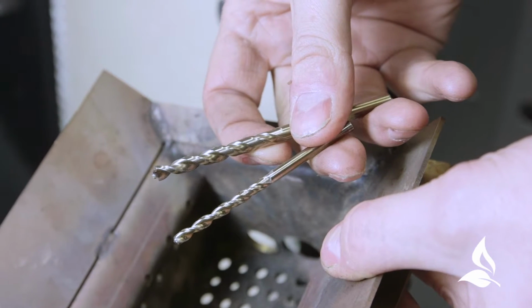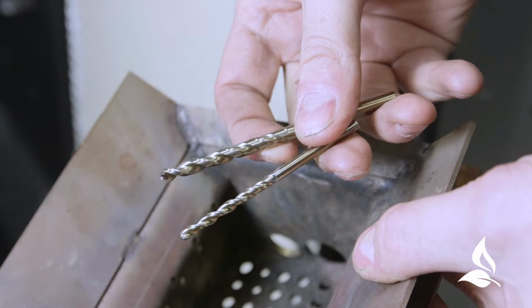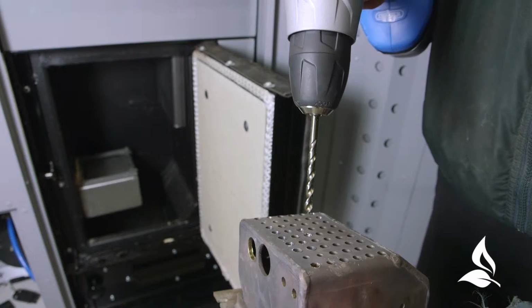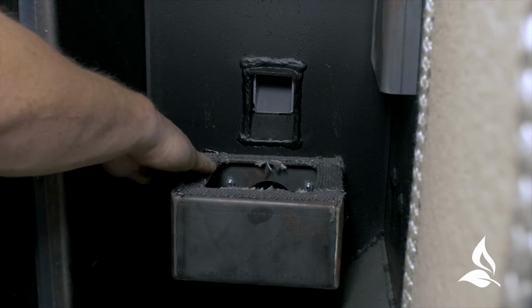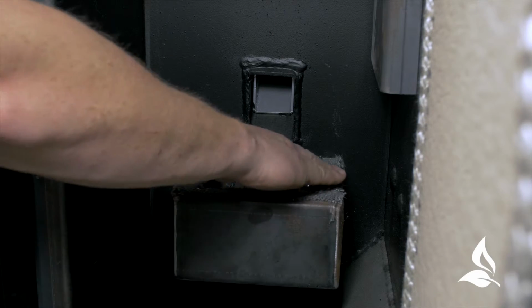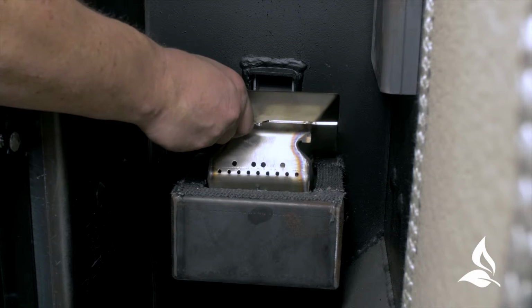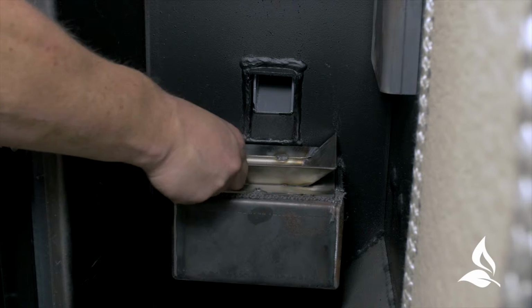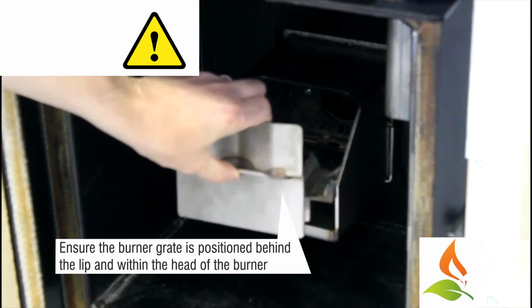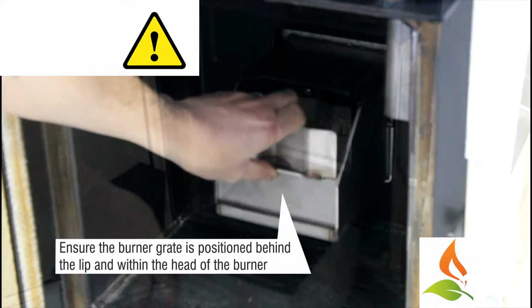This is done by drilling with a 5.5mm bit through the big holes to remove any carbon. Use a 4mm bit for the smaller holes. Check the rope seal that it maintains a seal when replaced in the holder. Ensure you replace the grate on the 15 and 18 kW in the correct position. On the 28 kW boiler, care should be taken to ensure that the leg of the grate is lifted over the lip of the burner head and sits securely in place.